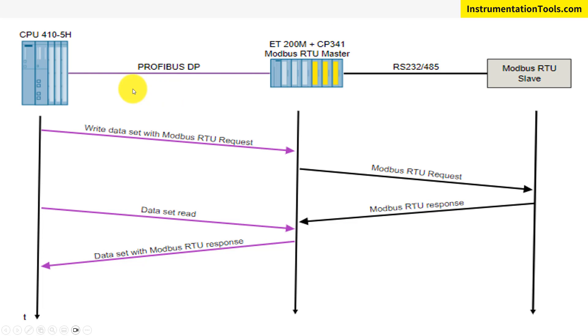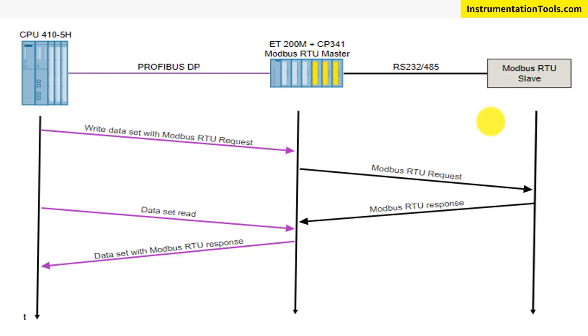The CPU 410 or AS station sends a Modbus RTU data request to the ET200M through Profibus DP. It then recognizes that it needs to pull data from the Modbus RTU slave connected via RS-232 or RS-485. If the device is alive and has data in its registers, it sends the Modbus RTU response. The CPU 410 sends a data entry request, and the Modbus RTU response is collected through CPU 410. This communication is slow, which is why it is not used frequently in industries.